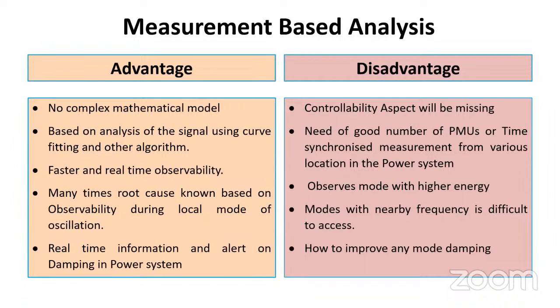Let's say 1.2, 1.5, 1.6 - that is in the inter-plant range. He knows there is a problem with the plant, so he will start detecting where this particular issue is, where this mode energy is very high. At that point he is going to ask whether something is happening in the system or not. He will start checking the MVAR, megawatt and MVAR values from the SCADA and the PMU data, to see which particular unit of the plant is having significant oscillation in the MVAR or megawatt values. Based on that information, he will immediately contact the plant, or the nearby 4 to 5 plants, telling them that if anything is happening, stop it.